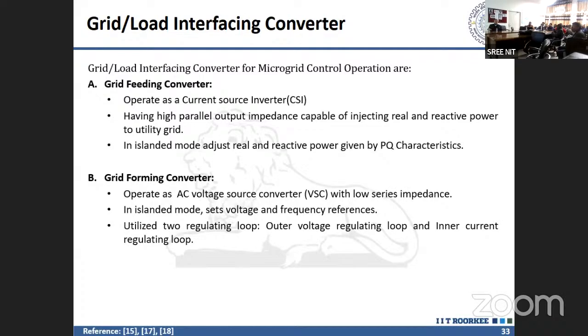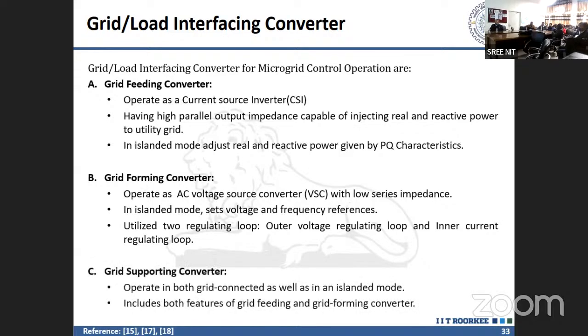Grid forming converters are those which work in the islanded mode. They are normally the voltage source inverter. This sets voltage and the frequency reference, and utilizes two regulating loops, outer voltage regulating loop and the inner current regulating loop. Grid supporting converters operate in both grid connected as well as in islanded mode, and include both features of the grid feeding and the grid forming converter.